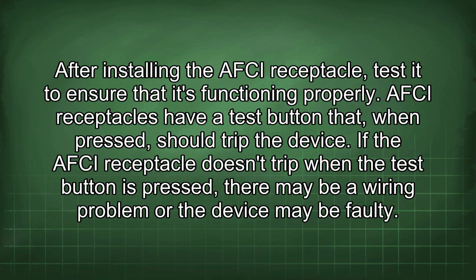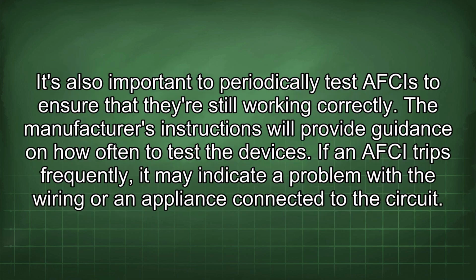After installing the AFCI receptacle, test it to ensure that it's functioning properly. AFCI receptacles have a test button that, when pressed, should trip the device. If the AFCI receptacle doesn't trip when the test button is pressed, there may be a wiring problem or the device may be faulty. It's also important to periodically test AFCIs to ensure that they're still working correctly. The manufacturer's instructions will provide guidance on how often to test the devices.